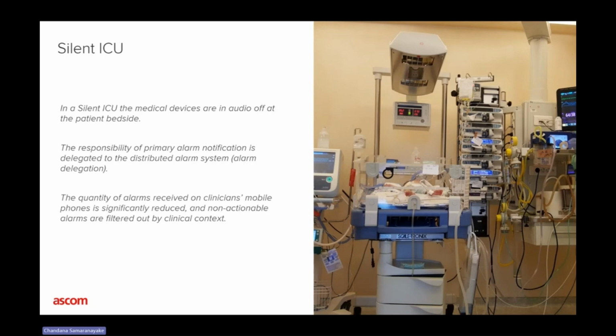The technology to create a silent ICU exists today. It's not science fiction. In a silent ICU, what happens is that the devices around the patient switch off their audio. They still generate alarms, but they don't actually sound anything at the bedside. And these alarms are basically taken over by a reliable alarming system that can actually move this information from the bedside to a caregiver's mobile device and sound the alarm at the mobile device. So in a sense, taking the sound away from the bedside to where the caregiver is, because the patient can't do anything with an alarm, right? It's worthless sounding that alarm at the patient bedside when the patient can't do anything with it. We need to bring it to the people who can actually act on it. So one part of it is actually removing that sound from around the patient.